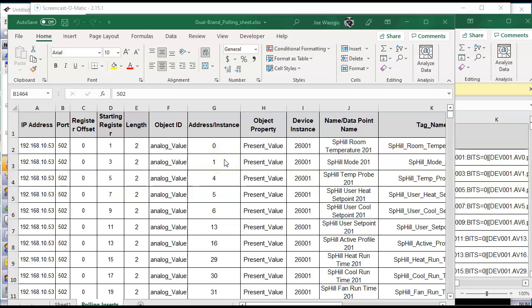We're going to make a video today on how to take a bunch of tags in an Excel spreadsheet and map them over. Actually, we're going from BACnet to Modbus TCP. We've got a project where they've got a bunch of tags in BACnet, the building automation control network product, and they want to map those over as a Modbus TCP slave device so some other SCADA or something else can talk to us and get this BACnet data over a Modbus TCP session.